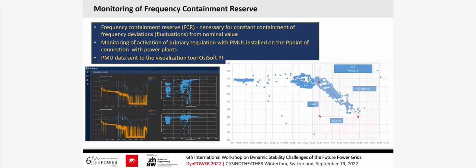One last slide from my side is just to show one possibility of a system in planning and monitoring: the monitoring of the frequency containment reserve. We have a system for automatic monitoring, and you also extract those data. When you plot the frequency-active power diagram, you can see the slope that practically represents the primary regulator characteristic. You can read megawatt per hertz and say whether this generator performs properly or not. So I will finish my part of the presentation now and continue with this part.